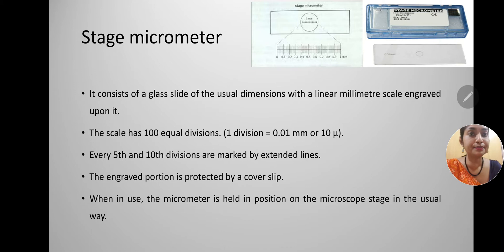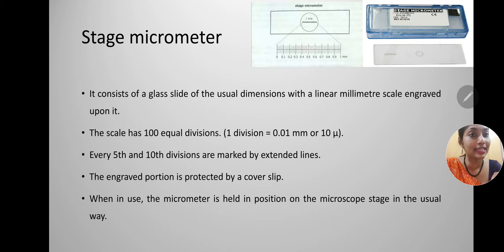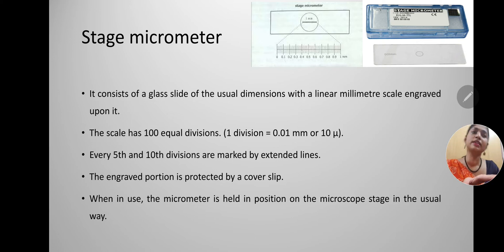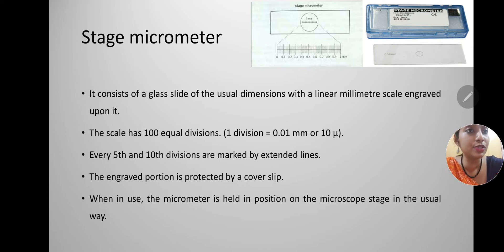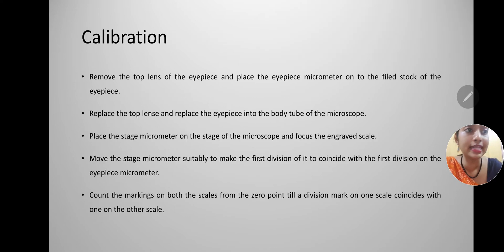The stage micrometer consists of a glass slide of usual dimensions with a linear millimeter scale engraved on it. The scale has 100 equal divisions, so the total scale is 1 mm and each division is 0.01 mm or 10 microns. Every fifth and tenth division are marked by extended lines. The engraved portion is covered with a cover slip, and when in use the micrometer is held on the stage of the microscope like a normal slide. In the image you can see the stage micrometer with 1 mm etching having 100 gradations. It is usually kept protected in a plastic box.